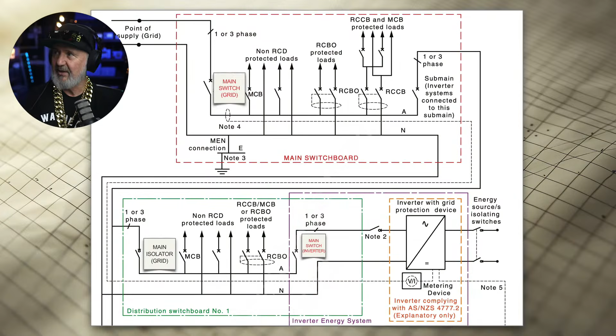The subboard has got a sub-main isolator, and that sub-main isolator now needs to be labelled main isolator with the indication that it's got a grid source. So that's a change - main isolator grid. We've still got our main switches for grid and inverter in red to differentiate them, the labels, from other circuits.